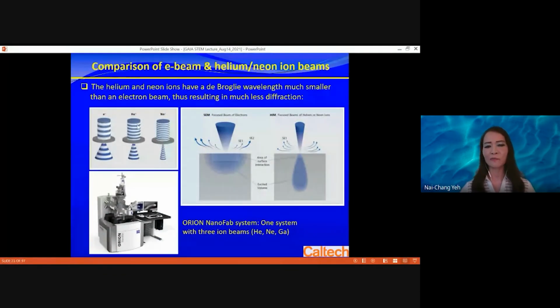This picture schematically shows that with an electron beam, the de Broglie wavelength is longer, so you get larger diffraction and the resolution is a little less. With a helium or neon ion beam, because the masses are bigger than electrons, the diffraction is smaller, and you can get good resolution without causing a lot of damage.